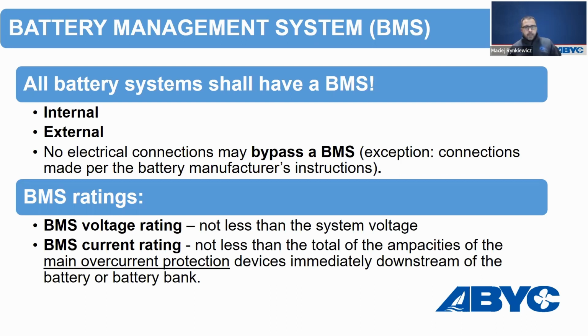The basic requirement is that no electrical connection can bypass the BMS. If you bypass it, it won't be able to shut down loads or the charging system. We heard stories of somebody fast-charging batteries with an external BMS, connecting a charger that didn't meet the charging profile, and overcharging the batteries. That's why we require nothing bypasses the BMS — only circuits designed by the manufacturer, like circuitry for cell balancing before the BMS, are allowed. And of course the BMS, like all electrical equipment, should have its own voltage and current rating.